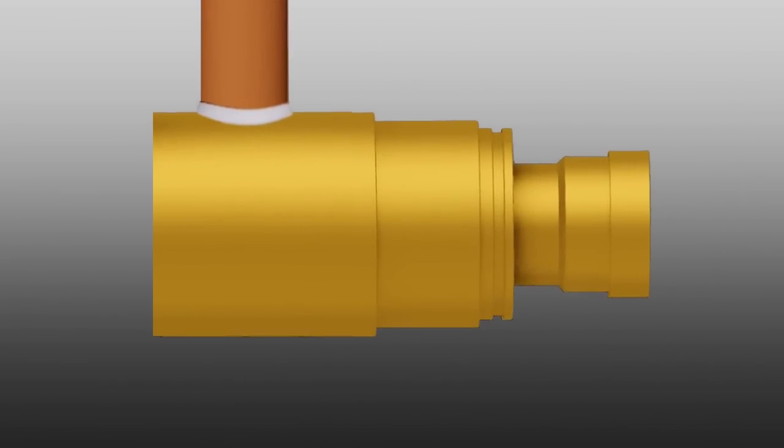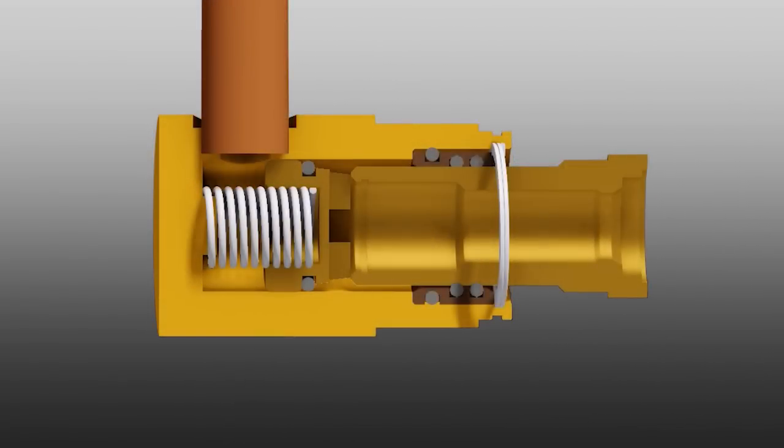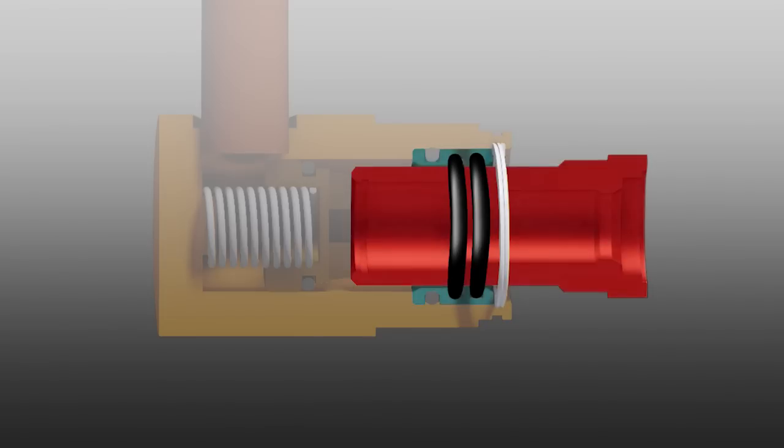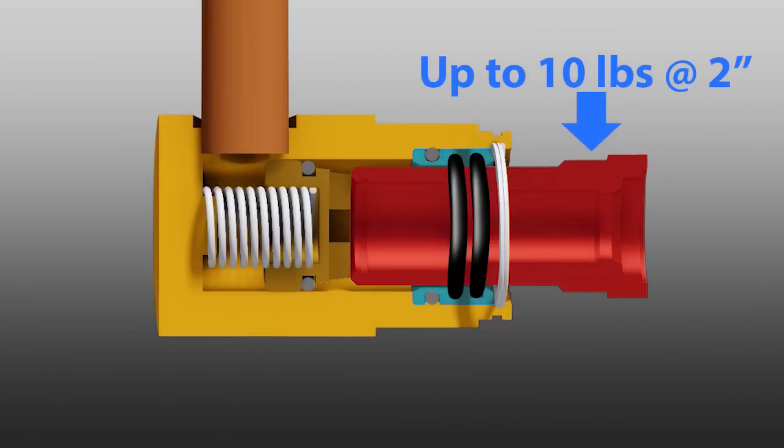The Tritec design is innovatively unique. A true dual O-ring design is incorporated with tight tolerances between the front brass shaft and back brass shaft sleeve, provides metal-to-metal support of up to 10 pounds of equipment at 2 inches from the outlet face. A distinctly more robust seal.